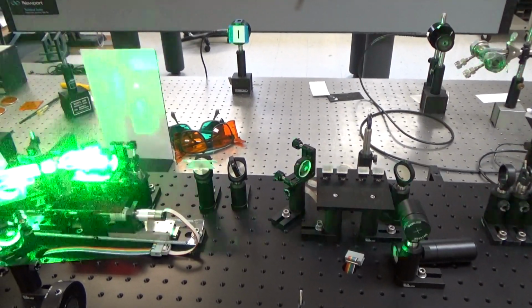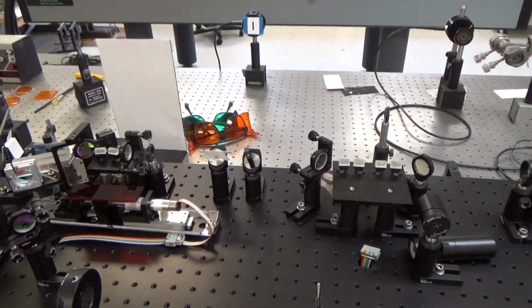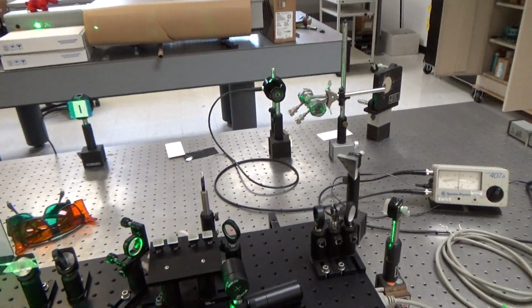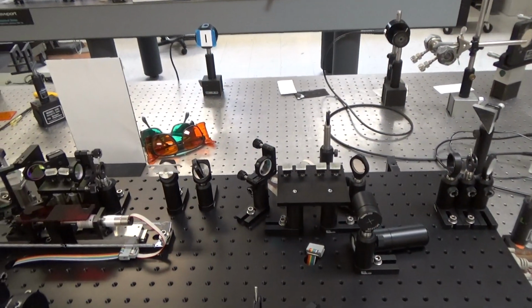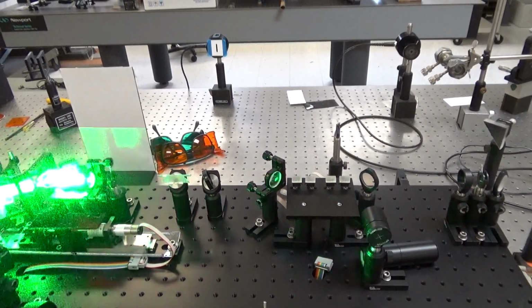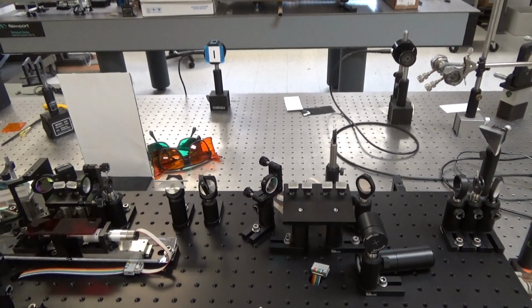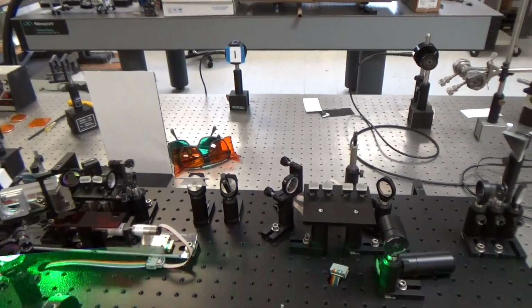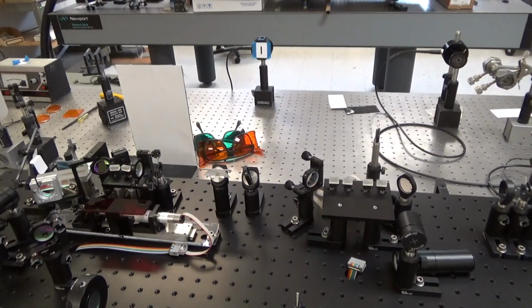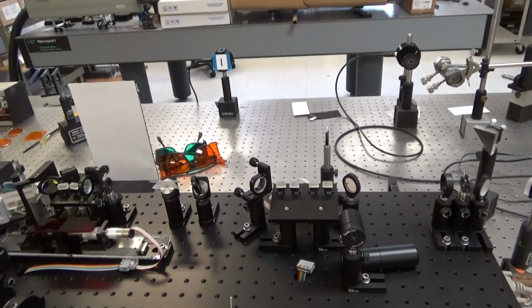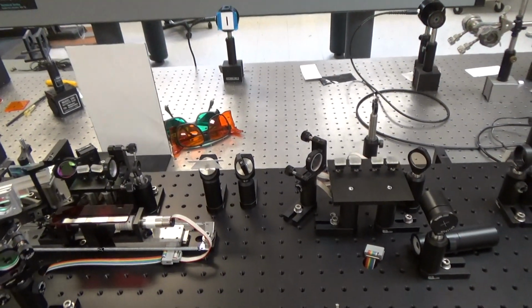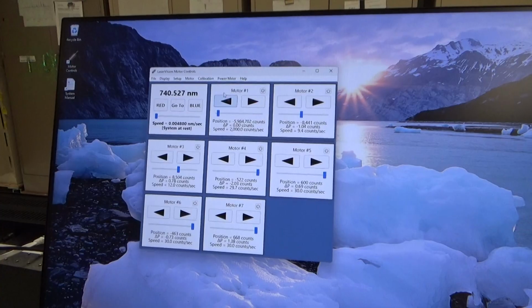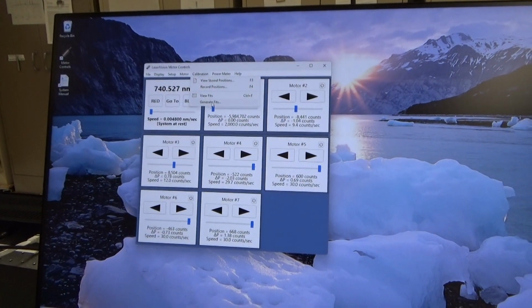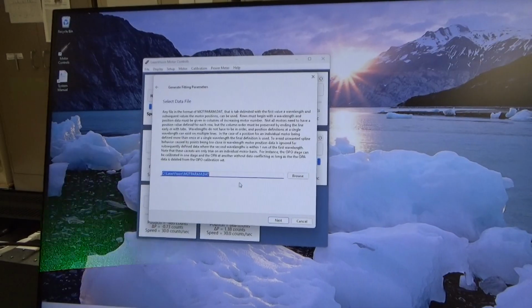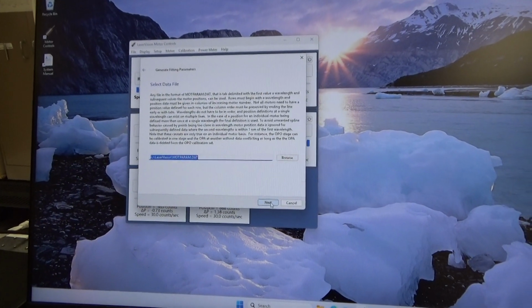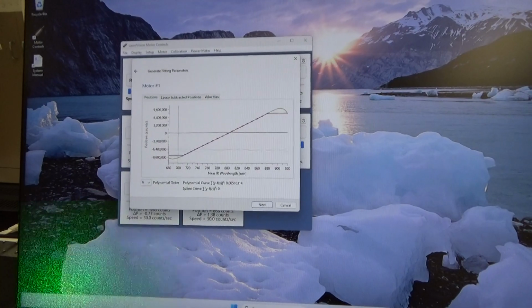and collect the data. Now I have a wavelength offset that we had discovered for the system using the silver gallium selenide cell, or the acetylene cell, and so when I go through the calibration routine, you'll see how the calibration takes this value into account. Okay, let's say I've collected the data now. I can go into the calibration, generate fits. I've got the new file moparam.dat, and it should step me through 7 motors here.